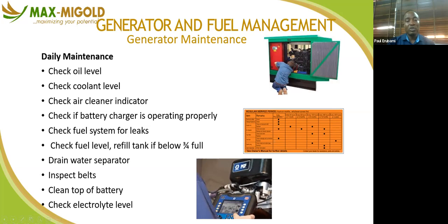If you don't do this, you assume that everything is fine, and just because you didn't check your oil level or water level, you end up knocking out your generator worth over 15 million, 100 million. So ensure you pay adequate attention to all this daily check. When you do this, you will not think of overhauling, as I do not encourage people to overhaul their generator. If you do proper maintenance, overhauling will be eliminated. So proper maintenance gives your generator adequate performance and reduces cost. Ensure you drive this on a daily basis.